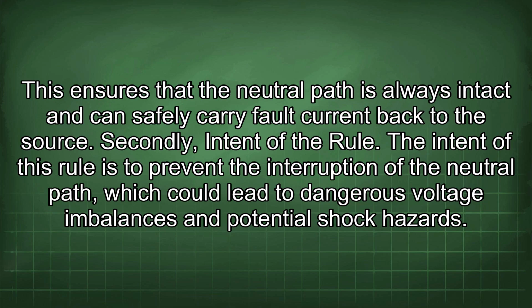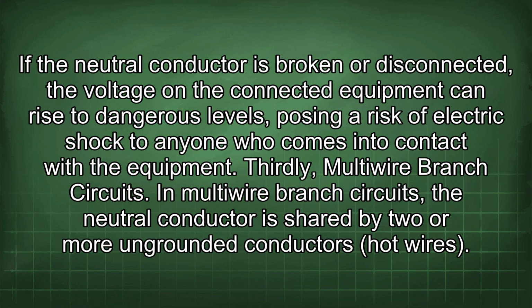Secondly, intent of the rule. The intent of this rule is to prevent the interruption of the neutral path, which could lead to dangerous voltage imbalances and potential shock hazards. If the neutral conductor is broken or disconnected, the voltage on the connected equipment can rise to dangerous levels, posing a risk of electric shock to anyone who comes into contact with the equipment.